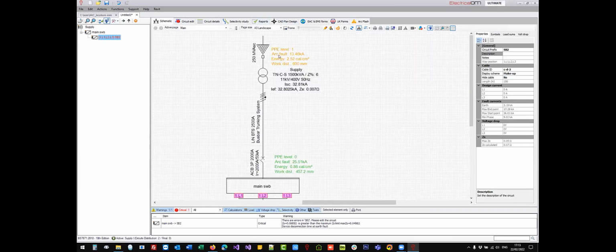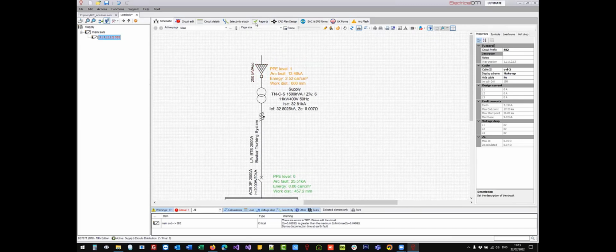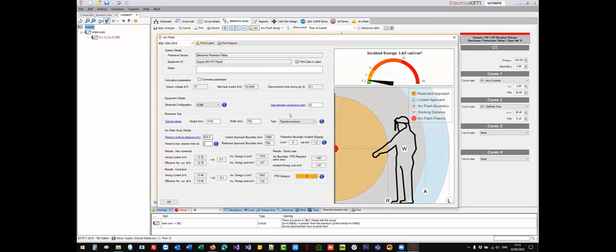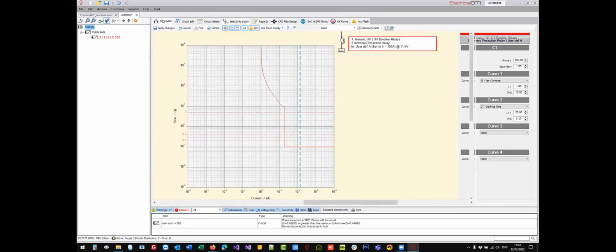Note that since I have modified my upstream equipment, the high voltage side equipment, I should go back to the supply, either from the selectivity study or from the supply editor, to make sure that there is no problem derived. Okay, so this is how you perform an arc flash study, how you build the network.